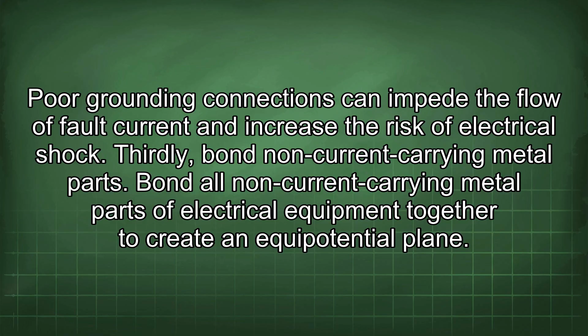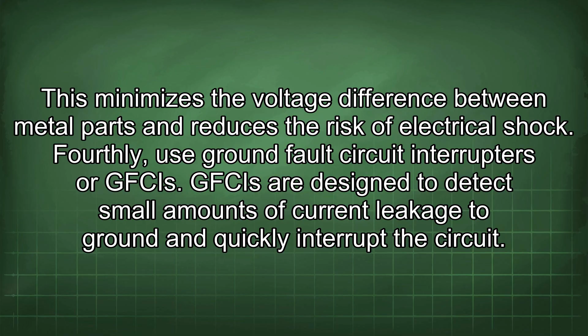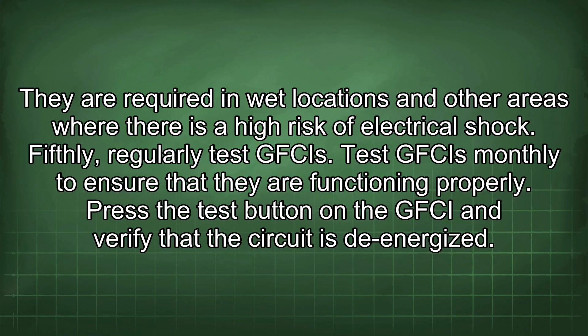Fourthly, use ground fault circuit interrupters, or GFCIs. GFCIs are designed to detect small amounts of current leakage to ground and quickly interrupt the circuit. They are required in wet locations and other areas where there is a high risk of electrical shock. Fifthly, regularly test GFCIs. Test GFCIs monthly to ensure that they are functioning properly. Press the test button on the GFCI and verify that the circuit is de-energized.